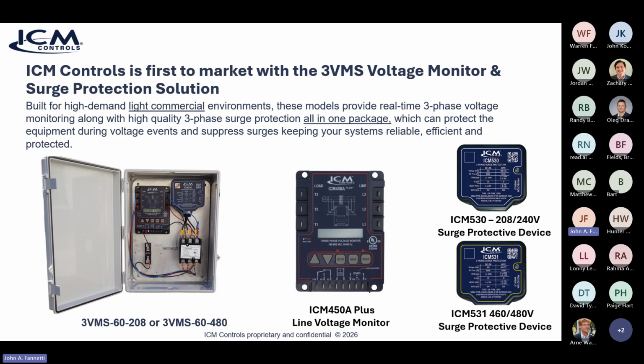They love our surge suppressors, but in some cases they want something where everything's all together in one, with a contactor in it that breaks you from the service voltage, and it's just all done for you instead of having to hand wire individual things. It doesn't necessarily mean that the 450A being installed by itself isn't still a good thing, or the individual surge suppressor. Sometimes you may only need one or the other, but a lot of times you want that whole package for the full circle of protection, and you can get it all in one with a contactor built into it so that you can actually break the service voltage.